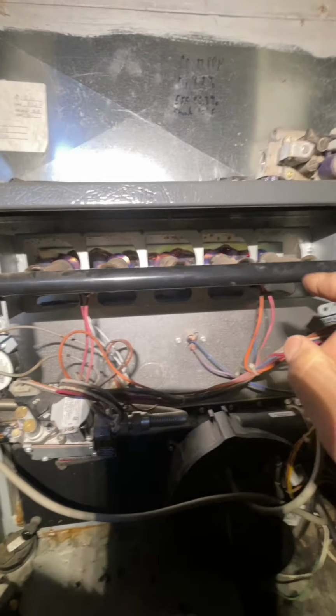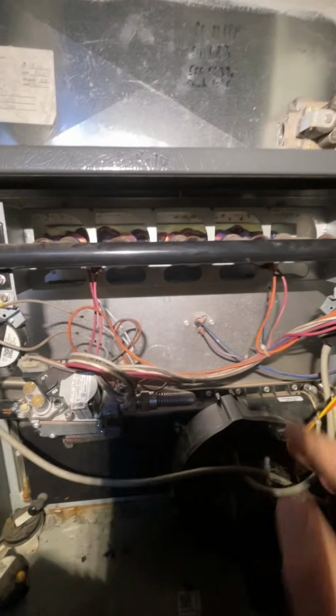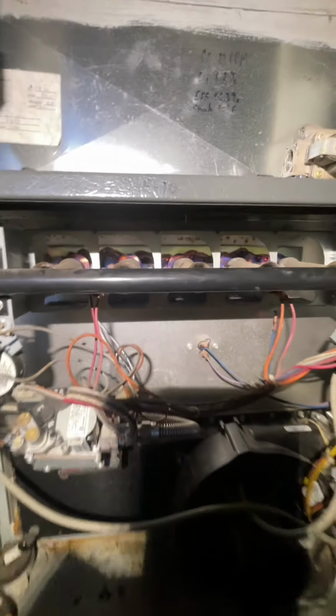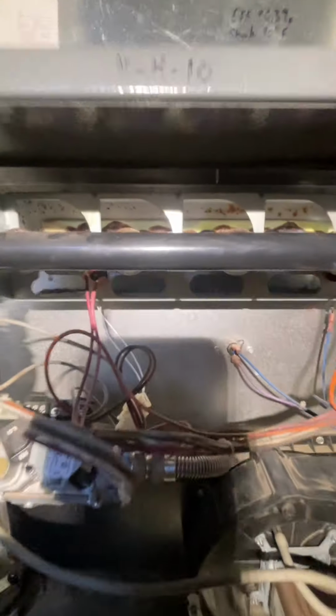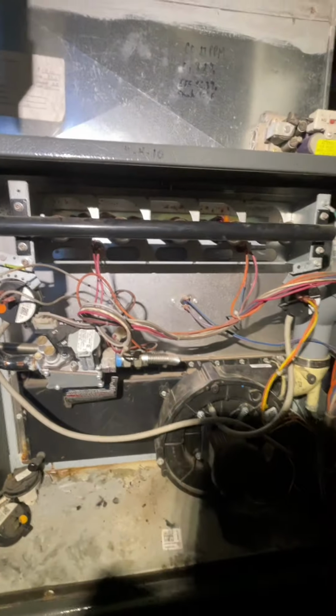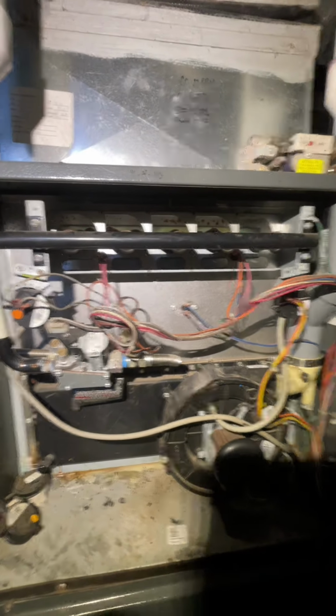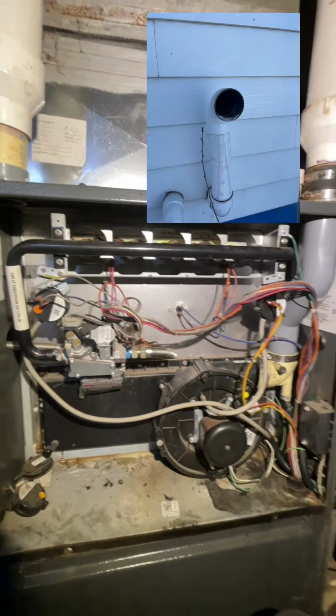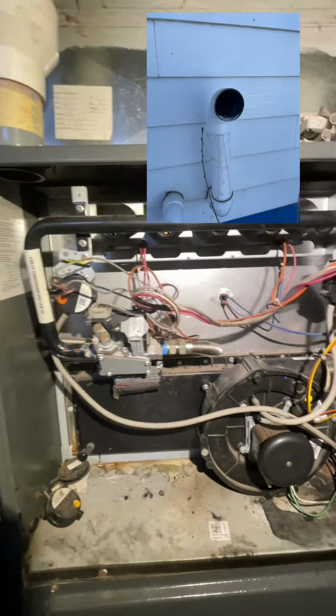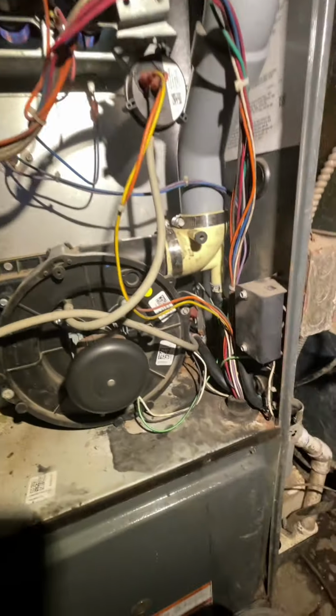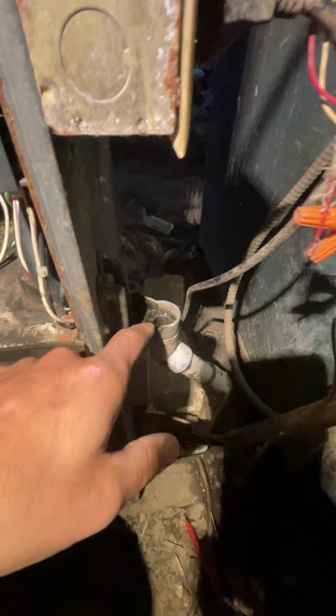The idea is that the inducer motor is supposed to pull that flame all the way to the back of the furnace. It's hard to see on camera, but it's real yellow and not getting back there. I'll also include a picture of the exhaust pipe. The exhaust pipe is just black, man, looks like diesel exhaust or something. You can see there's a fair amount of soot in there too.